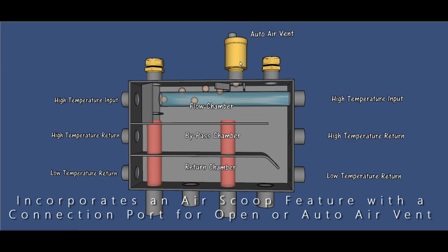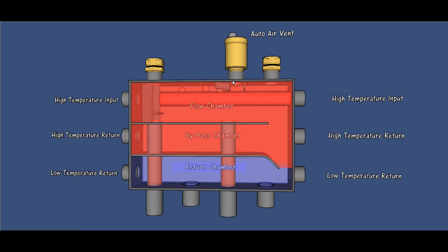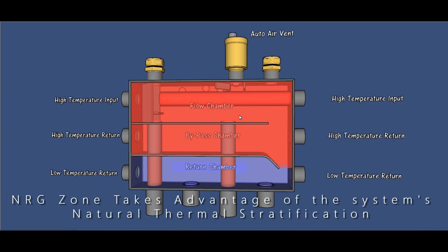You would put an automatic air vent here, or an open expansion vent, or any way of exiting air from the system. Within that you have a trap created that catches any air bubbles and allows them to escape. So if the manifold is being filled with water from a boiler, the top chamber is hotter.